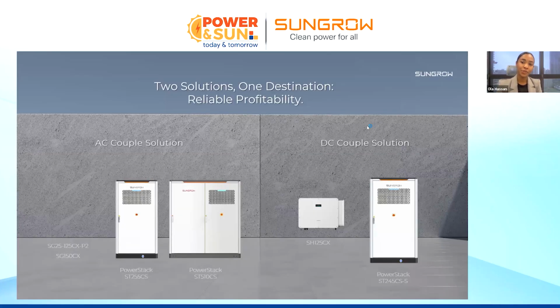So now we have recently introduced a new player to the market, which is the DC coupled solution. Earlier we had the AC coupled solution, which we call the power stack. The AC coupled solution is a cabinet that has the PCS, power conversion system, and battery racks inside as well. And it works with the PV inverters. The PV inverters will convert DC to AC, injecting into the point of connection, and then your batteries are AC coupled. You can install it on the same point of connection. So this is very suitable for retrofitting. Perhaps you already have a solar system installed, but now maybe the regulations have changed and you want to include a C&I energy storage system. This is very simple to add. You will just add the energy storage system on your point of connection, which is AC coupled.